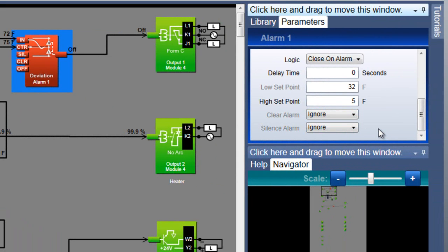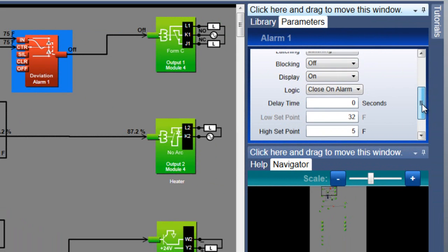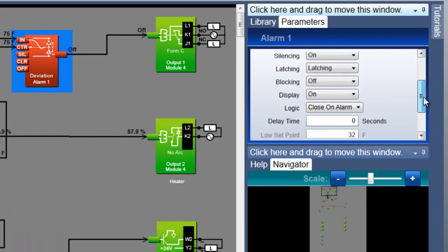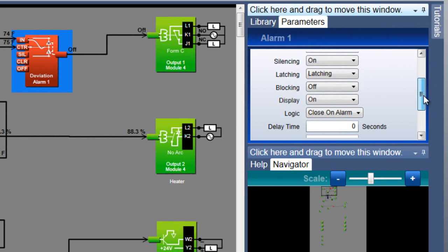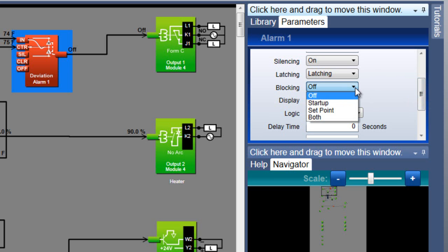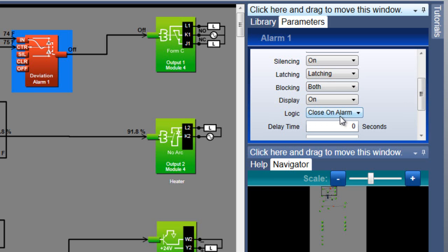However, sometimes deviations are expected, and alarms can be a nuisance. When the power is turned on to a machine, it normally takes time for the control loops to reach setpoint. Also, when you change a loop setpoint, it takes time for the loop to reach the new value. The alarm's blocking feature can be set to ignore alarm conditions for setpoint changes and startup. Alarm blocking allows a system to warm up after being powered up or to be adjusted without experiencing nuisance alarms. Set alarm blocking to prevent alarms before the monitored signal has first come within the normal operating range defined by the alarm setpoints.